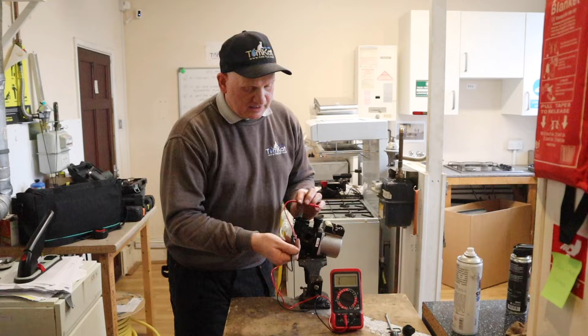Now again, I'm using my multimeter and I've got it set on the 2K ohms range. What I'm going to do is go between the neutral and the live, and we should be getting between 100 and 250 ohms. So, neutral and live, what are we getting? 178.